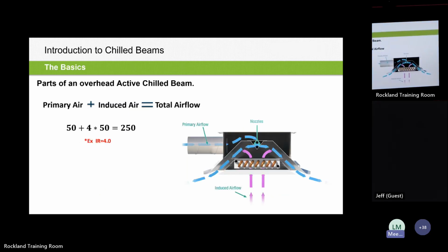All right, so Matt talked about this earlier. Essentially, we're only running a fourth to a sixth parts of primary air to the chill beam. And again, you're usually mixing and moving a lot more air changes than a traditional system, just by the nature of that induction process.